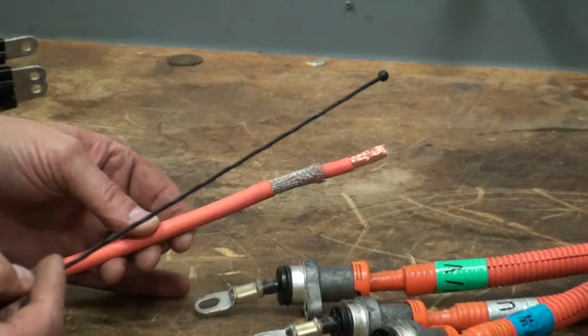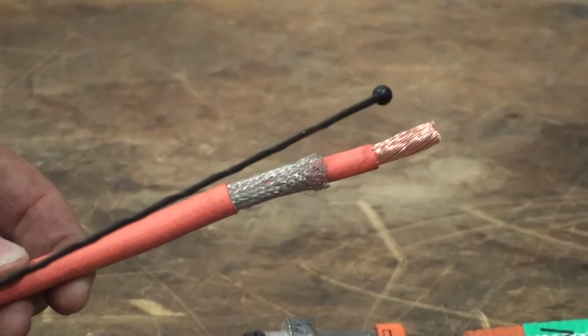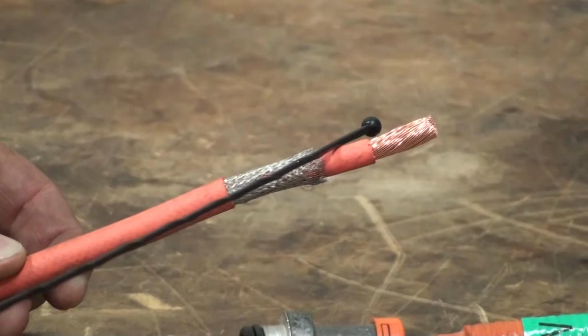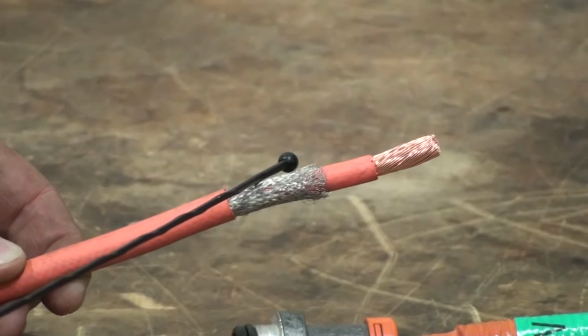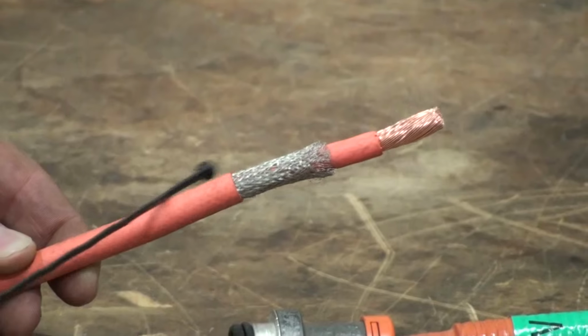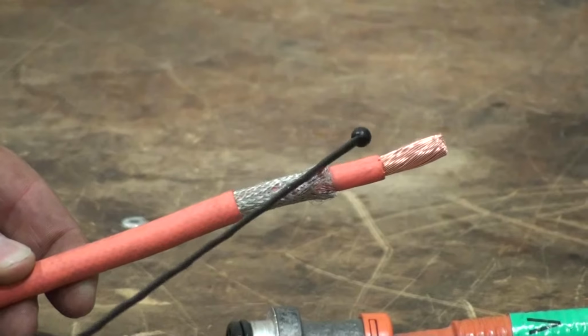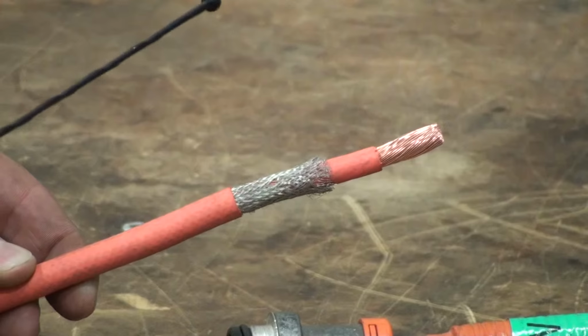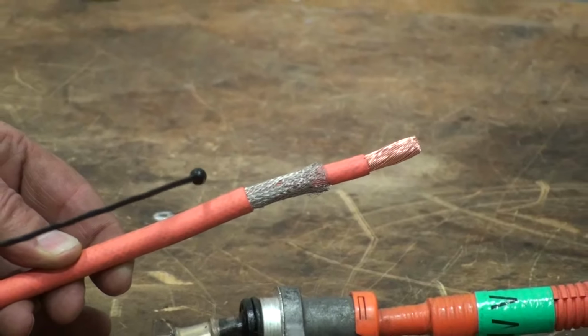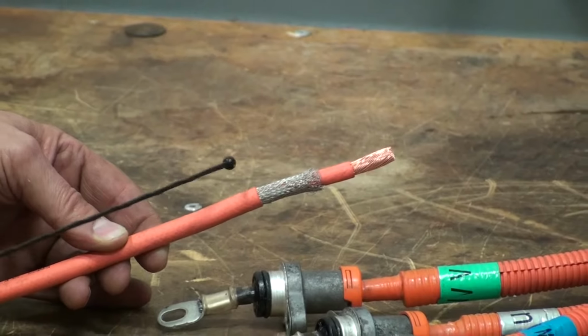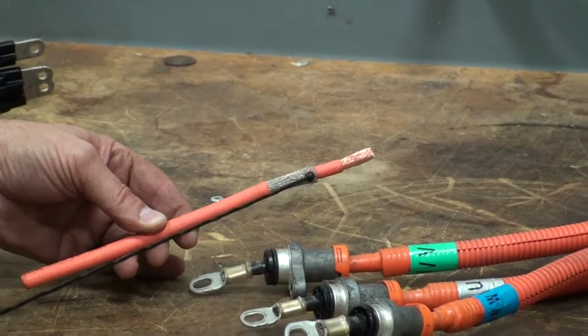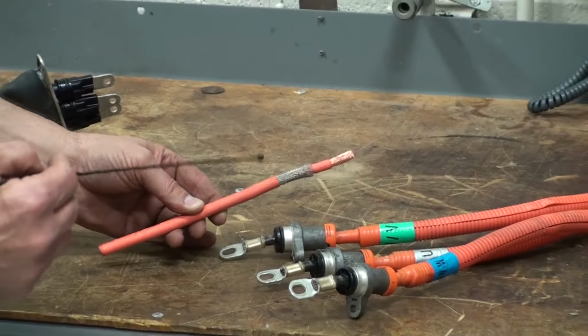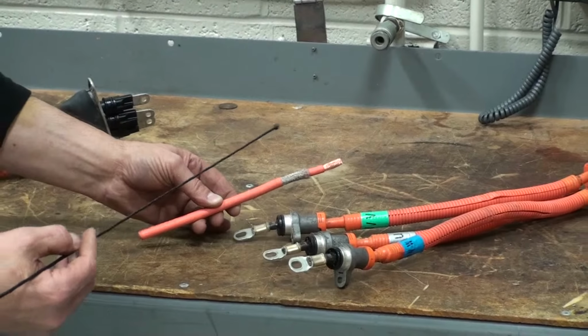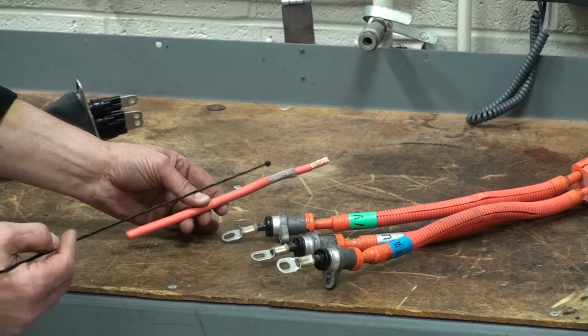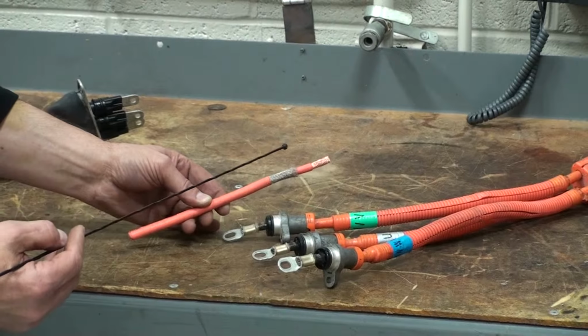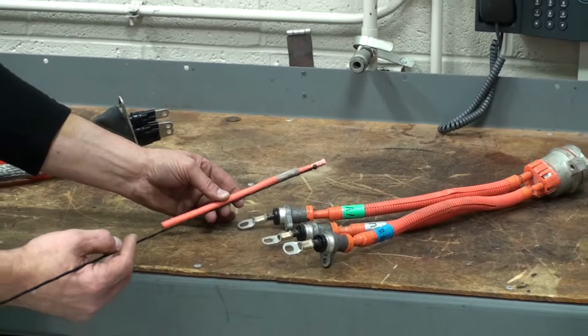You have a copper core, you have an outer sheath on the copper, then you have the shield itself, and then you have an outer sheath. Now the shield is made up of either aluminum or copper, and it's meant to keep the high frequency electrical switching noise from getting out of the cable, or any high frequency noise from getting into the cable that would interrupt signals or cause some interruption in the signal between the power inverter and the electric machine.